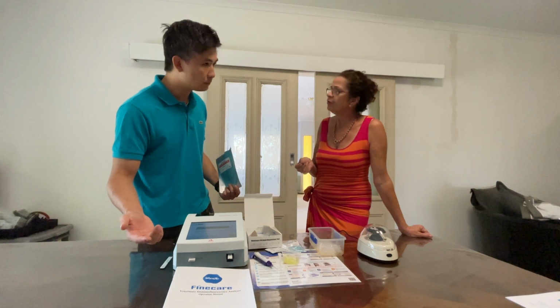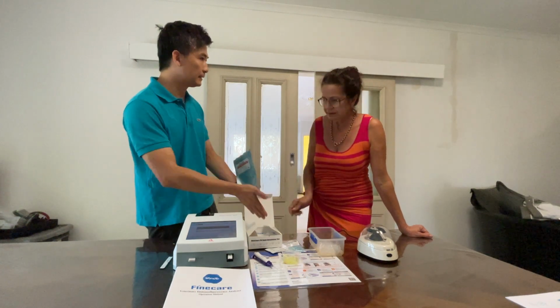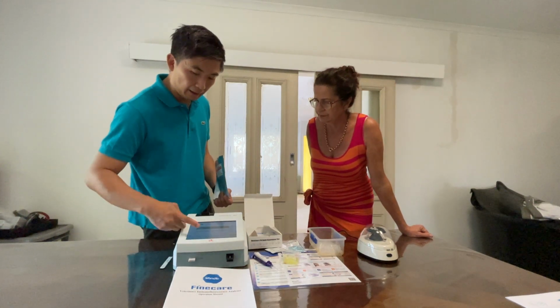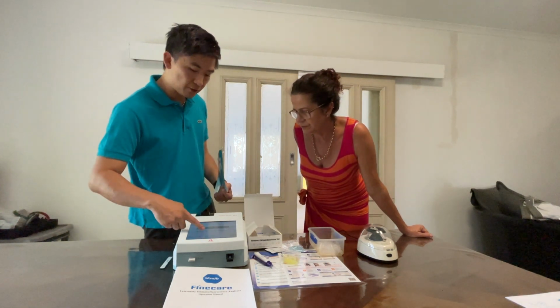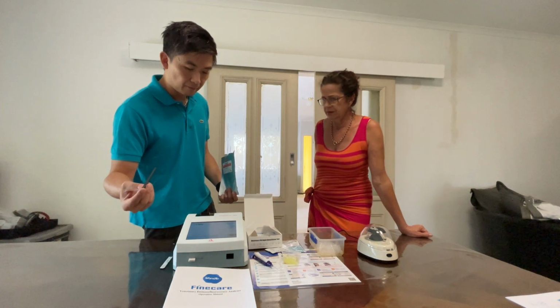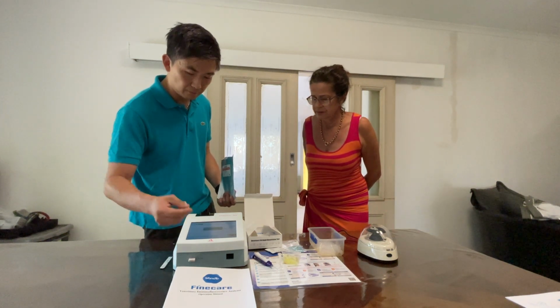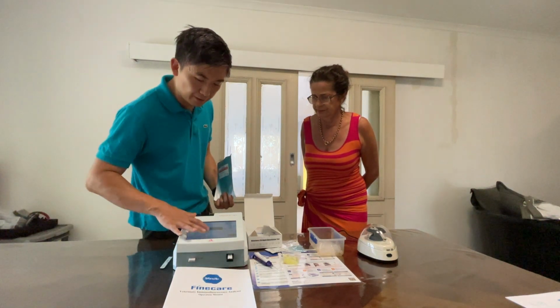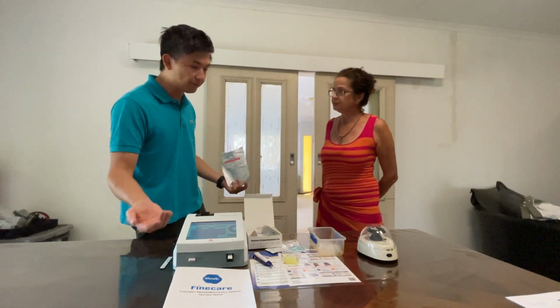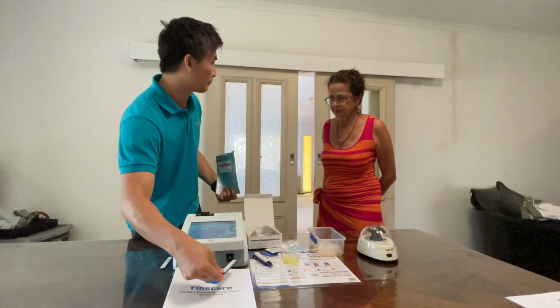Now, do I do that every time I turn the machine on? If you want to, you don't have to. I think it's good enough for the 10 tests in the box. If it tells you to manually override, just press yes. Okay, I've taken it out. Let's do it again. It's a good idea to leave the cartridge in while you're running the test. Okay, so we've got a result. It shows it's less than a certain amount, and that's a control. So we're happy with that. If you want to save the record, you can always press print, and it will do a quick printout. Otherwise, the calibration is done.